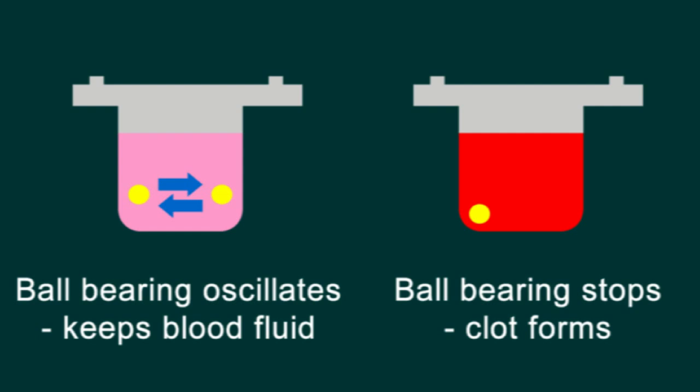Alternatively, we use a standard curve where 50% of the time taken for the clot to form is used as the reference point. In the olden days we used to use light intensity. Using light intensity is a good method, but there are drawbacks — for example, if the sample is lipemic, meaning the sample is very milky, light cannot pass through it because it is already a turbid sample.